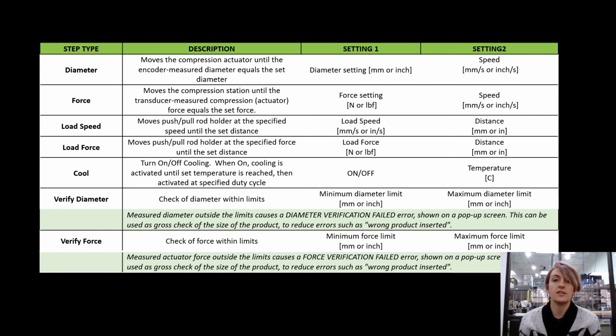In the LX manual, you'll find this table that lists all of the step types available for your machine. We can discuss the main ones here. The first one, the diameter step type, is a way of controlling the compression station diameter. With this setting, you can tell the machine that you want it to crimp to a given diameter, and it will crimp that small regardless of the force needed to crimp your stent down to that size. Conversely, you could choose to use a force-controlled step, in which case you're telling the machine how hard you want to crimp on the stent, and then it will end up at whatever diameter is necessary to reach that force set point.